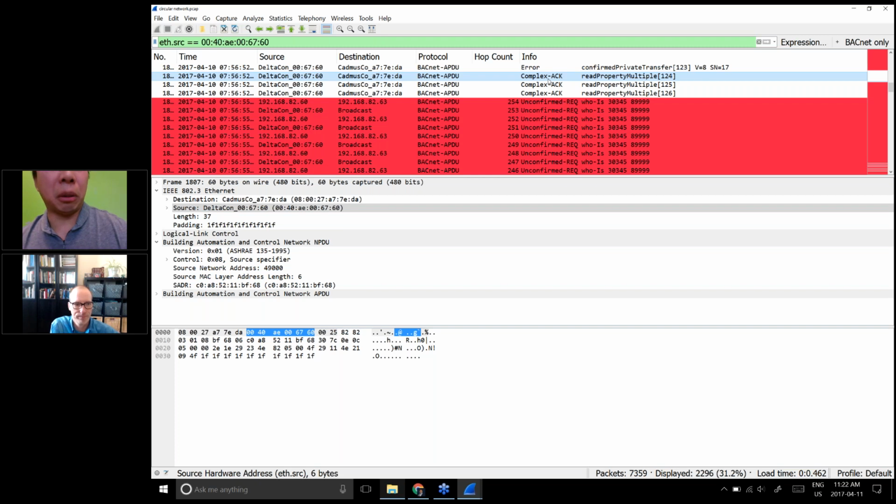Yep. So Greg, I'm just going to summarize what you just said there. If you suspect a circular network, one easy way to look for it is if you have a lot of broadcast. That can be one of the first hints of it. Then you use the filter, as Greg said, which is bacnet.hopc, hop count, less than a small number. It doesn't really matter what number you use. You can use 50, it could be 100 or something, and it would still work fine.